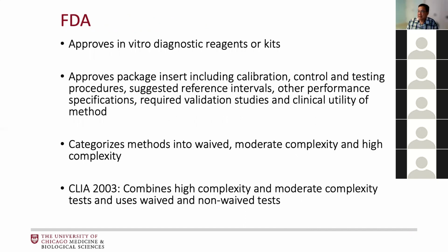Okay, just to expand a little bit on the FDA role, it approves IVDs and kits, and in the kit, it approves all the package inserts. Especially in the clinical lab, whenever you buy an FDA approved test, the first thing that comes out of the box is the package insert, which tells you how to calibrate, what control and testing procedure to use, what the suggested reference range should be, and what the performance specifications are.